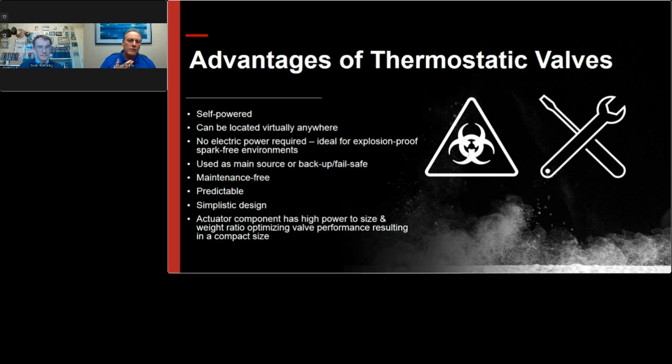One of the biggest advantages of thermostatic valves is that they're self-powered. They require no auxiliary power of any kind. They can be located virtually anywhere, oriented in any position, with no extra wiring. There's absolutely no electric power required, which is ideal for explosion-proof and spark-free environments. They can be used as a main source or backup for fail-safe, and they're maintenance-free.